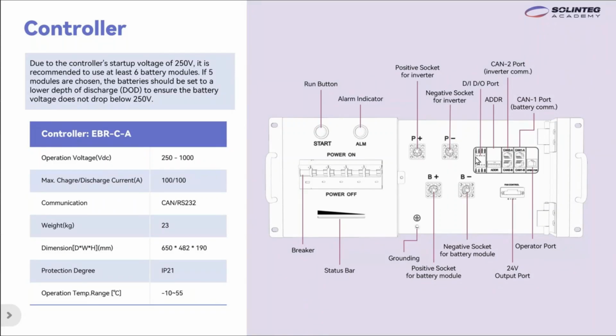Here is ADDR for the physical address of the controller. Here is the CAN2 port for communication with the inverter, and here is the CAN1 port for communication with the battery. Here is the breaker, and here is the status bar showing the working status and existing capacity.